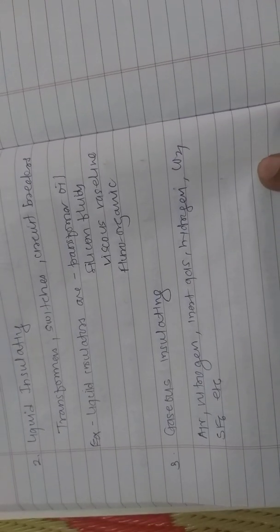It is a general observation that air provides insulation between overhead transmission power lines without any cost. In plenty of uses, it is present as a part of electric devices, whether we plan it to be there or not. Pressure has a decided effect on the dielectric strength of all gases. Higher pressure increases its ability to insulate. So this is regarding gaseous insulating materials.